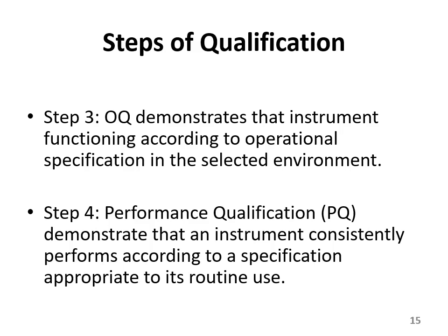Okay, and step 5, as I have told you earlier, that I haven't given in the phases as it's not the part of your curriculum, but this is the part of the qualification. So just for your knowledge, maintenance qualification, MQ, describes and documents any maintenance required on the equipment.